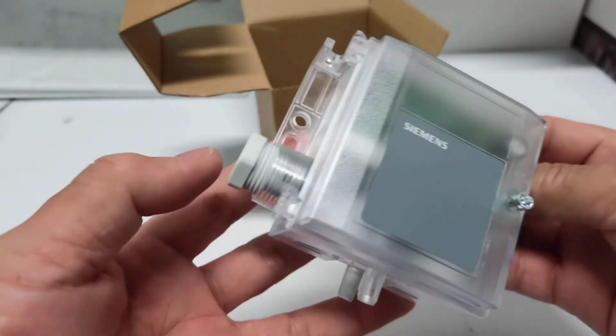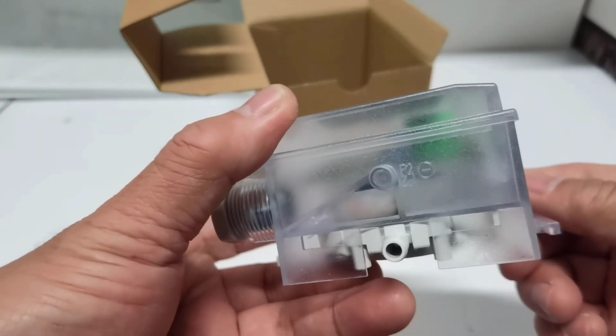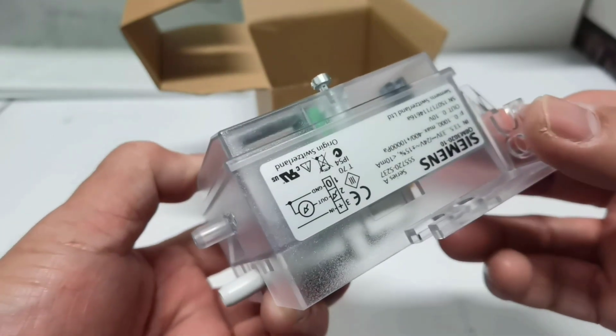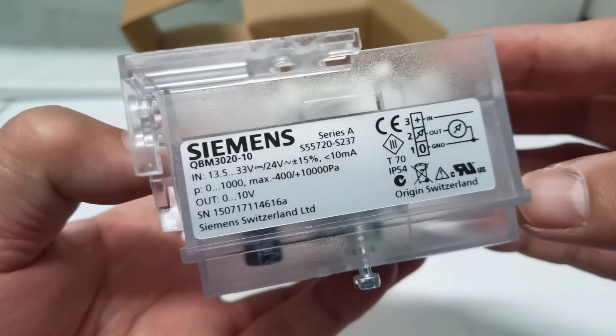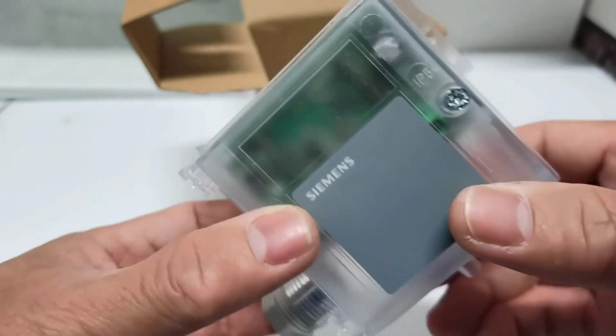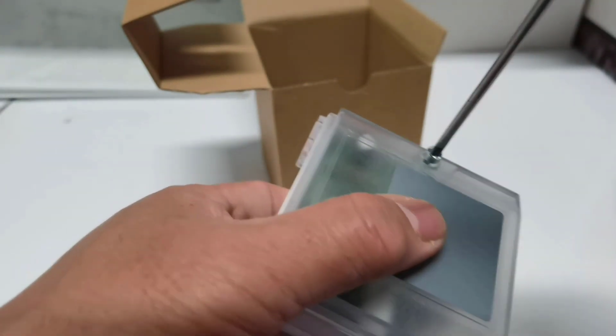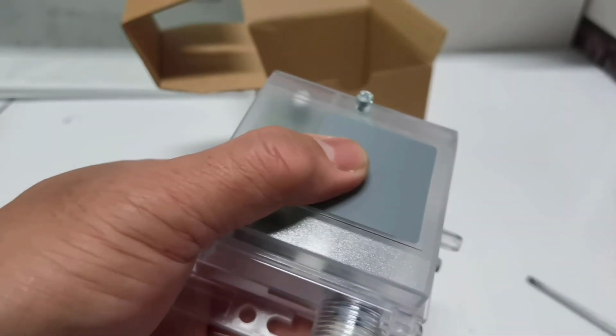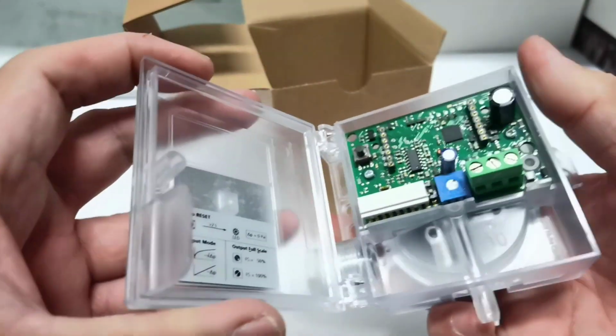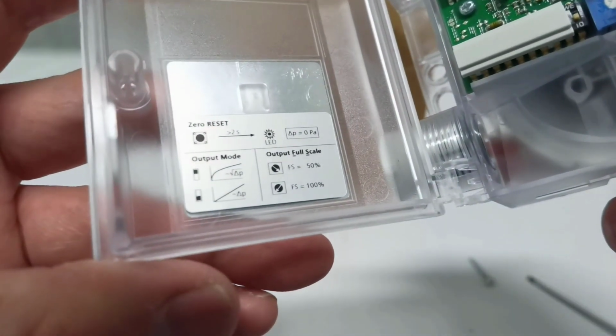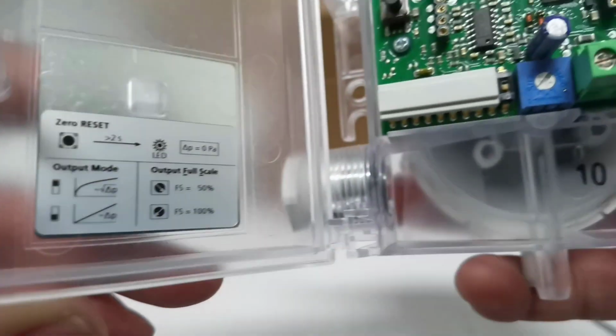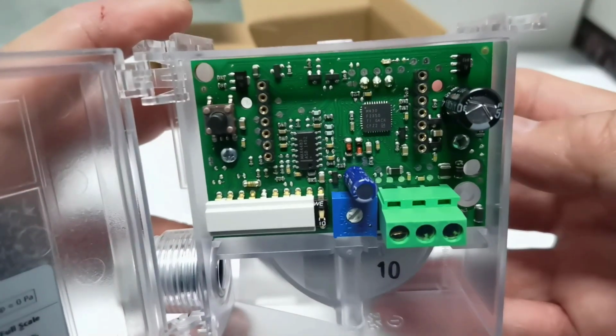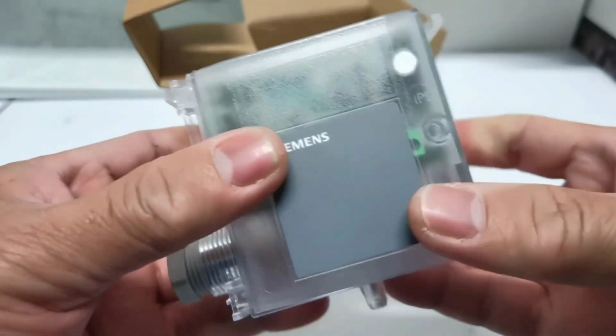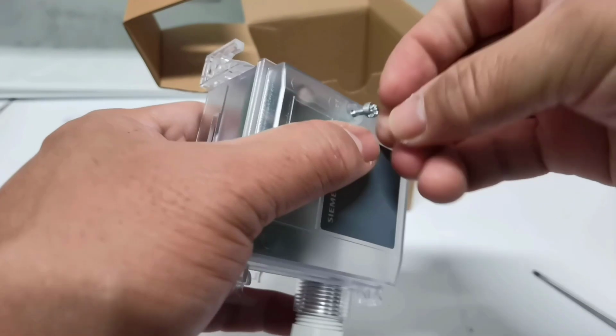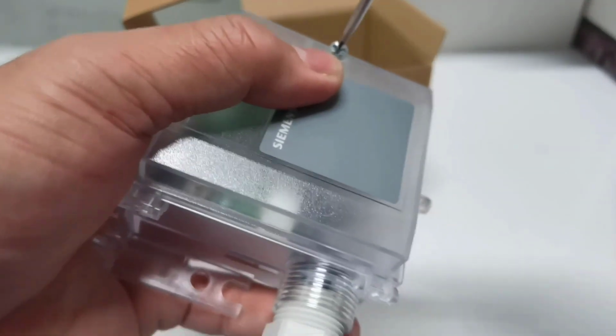This one is a differential pressure sensor with an operating voltage of AC 24 volts and an output signal of 0 to 10 volts DC. The differential pressure sensor acquires differential over and under pressure of air and non-aggressive gases, if a high degree of measuring accuracy and quality is required. It is also used for measuring volume flow via differential pressure, since the output signal can be set to extracting the root. It can measure the slightest differential pressures in ventilation and air conditioning ducts. The sensor acquires the differential pressure using a silicone rubber membrane and ceramic bar. Depending on the type of sensor, the sensor generates a linear or extracting the root signal of 0 to 10 volts DC.